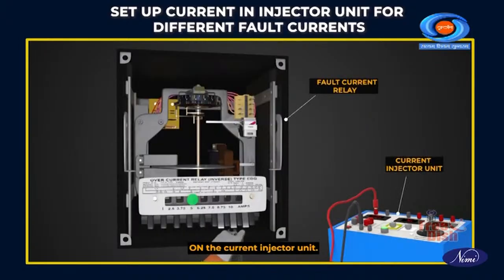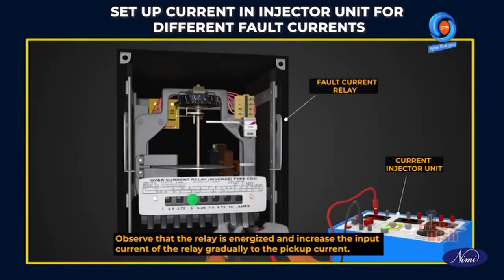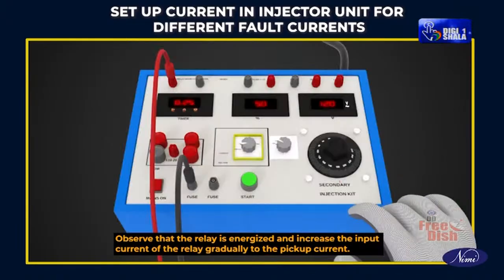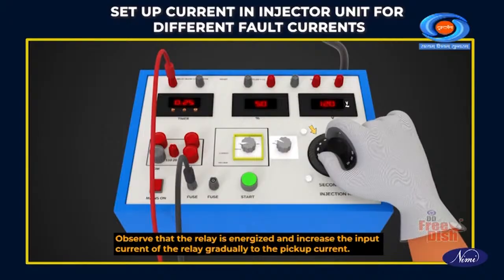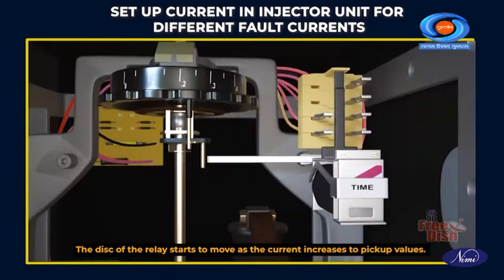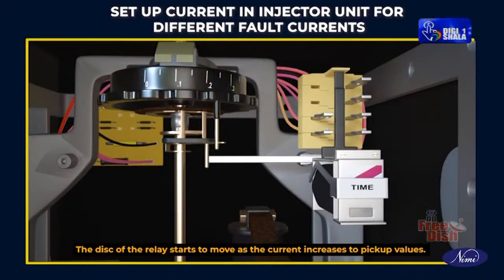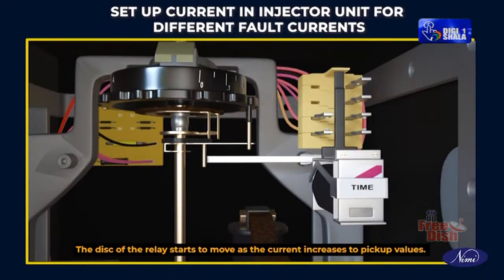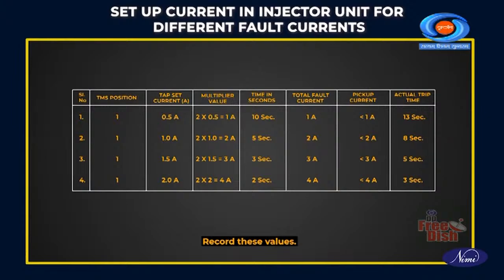On the current injector unit, observe that the relay is energized and increase the input current of the relay gradually to the pickup current. The disc of the relay starts to move as the current increases to pickup values. Record these values.